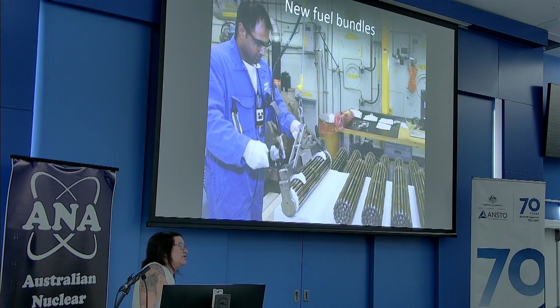However, things break, including fueling machines. At Bruce and Darlington, we can fix them online, but at Pickering and New Brunswick Power, they have to take the unit down to fix them because they're a bit different design. In theory, there's a unit that has run for 650 days in Ontario - one of the units at Darlington, might even be 700 - and there's one at the Bruce that's run for more than, or up to almost, 2 years. The theory was we're going to fuel online so we don't have to shut down to fuel, like you do here at the OPAL reactor, and like most pressurized water reactors and boiling water reactors do around the world.